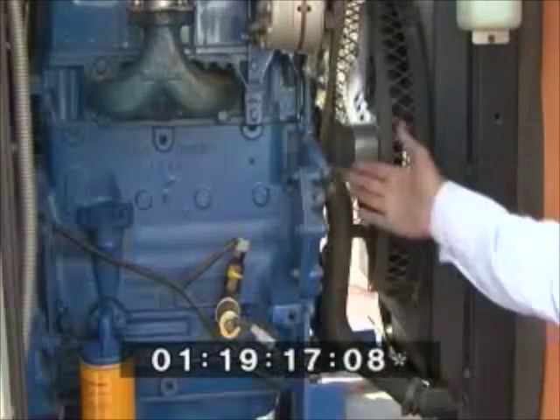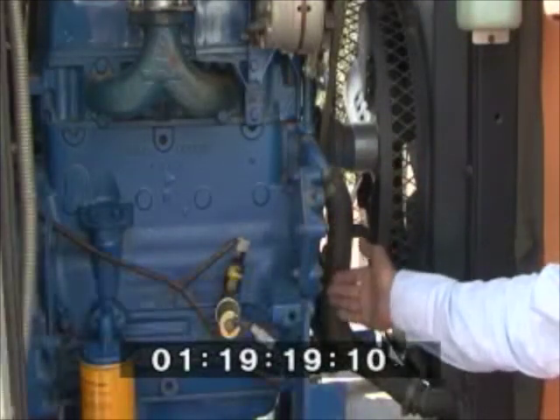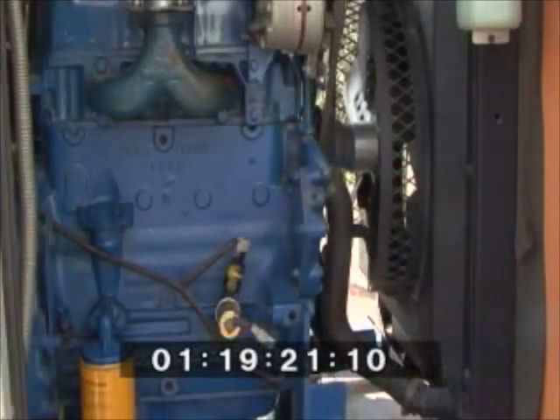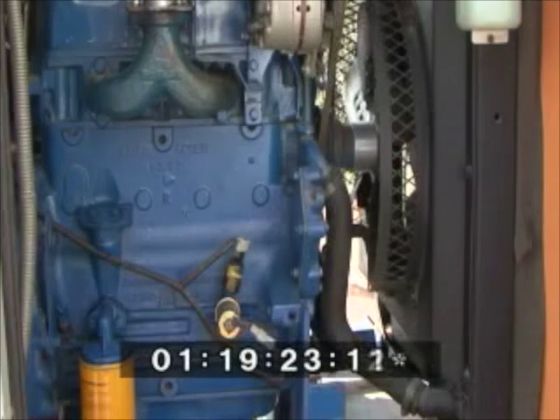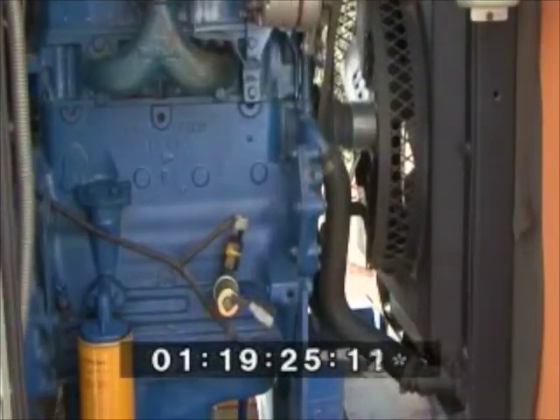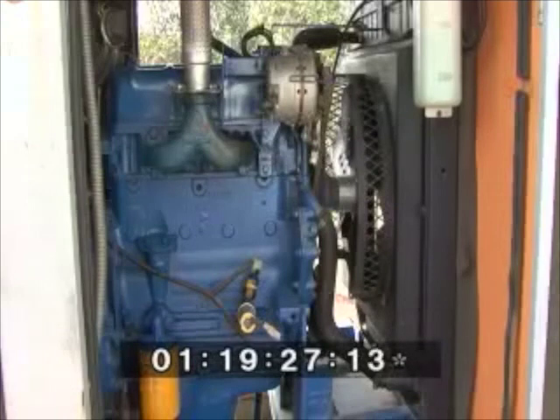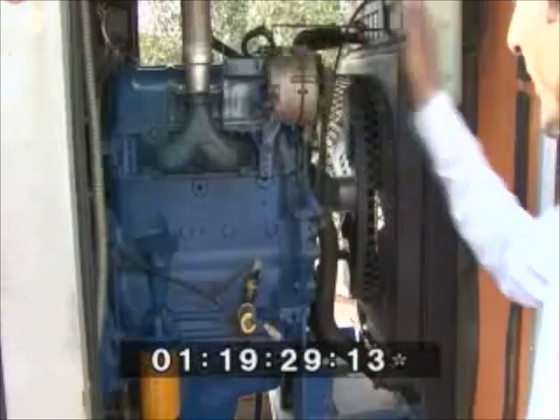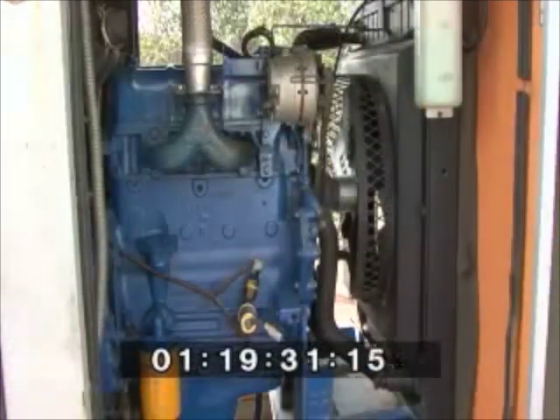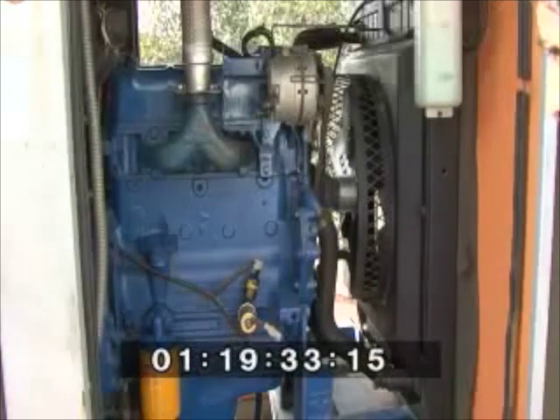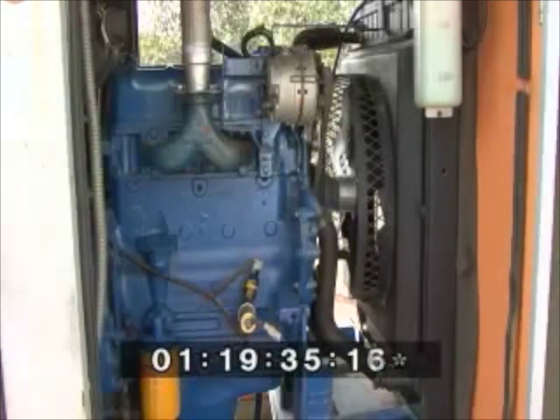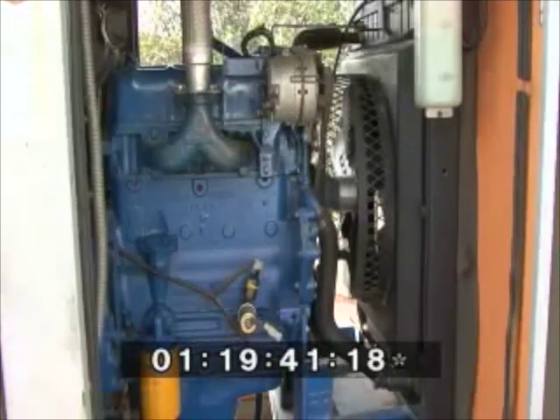All the nuts and bolts in the DG should be checked for tightness. The nut bolts of alternators, AVM, DG fan, silencer, etc. may get loose due to the vibrations while running.